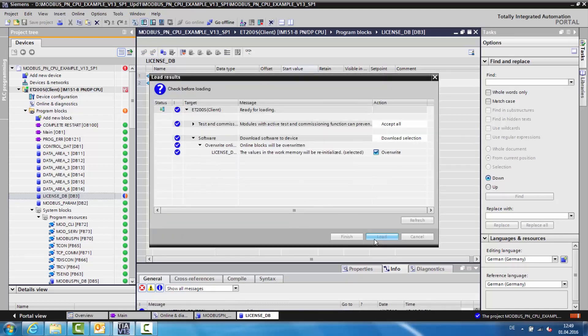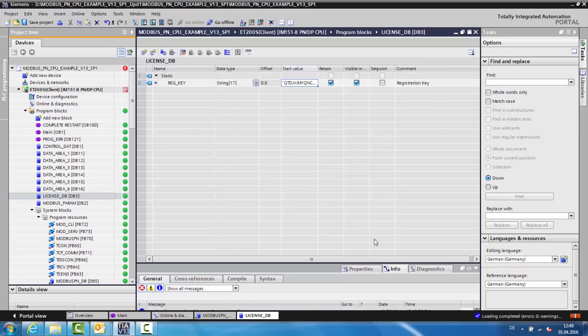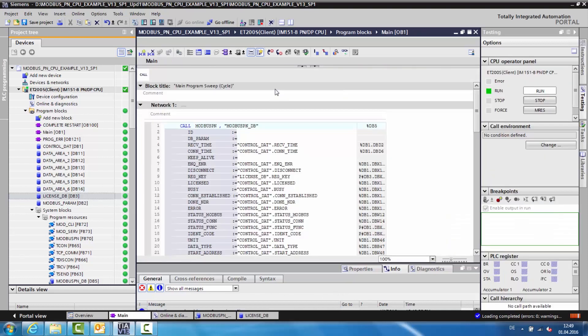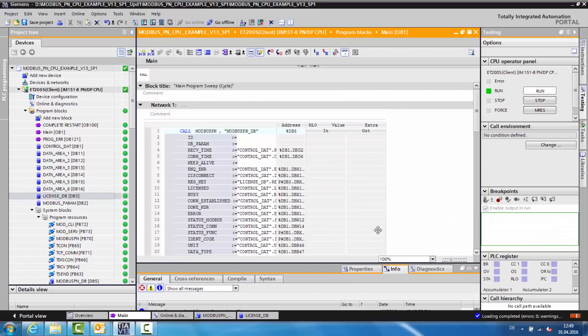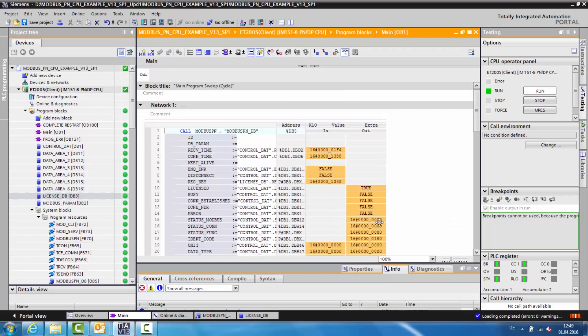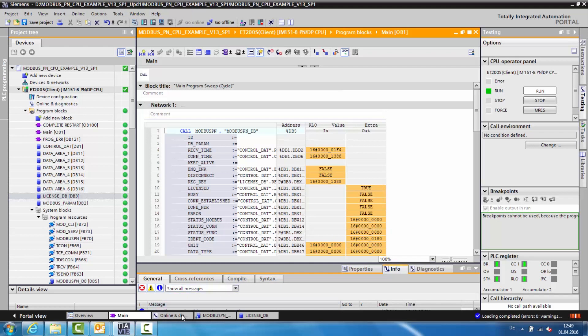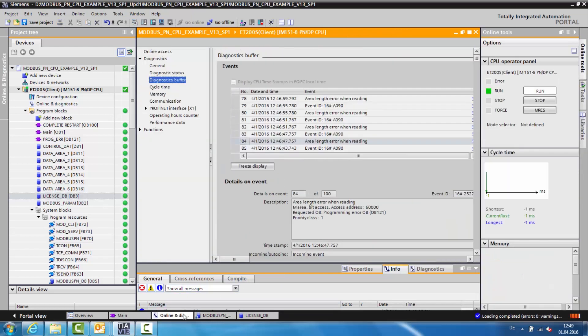Now the Modbus TCP block is licensed on the CPU. The LED on the CPU is no longer blinking. The block output no longer indicates A090, and there are no longer any entries in the diagnostics buffer.